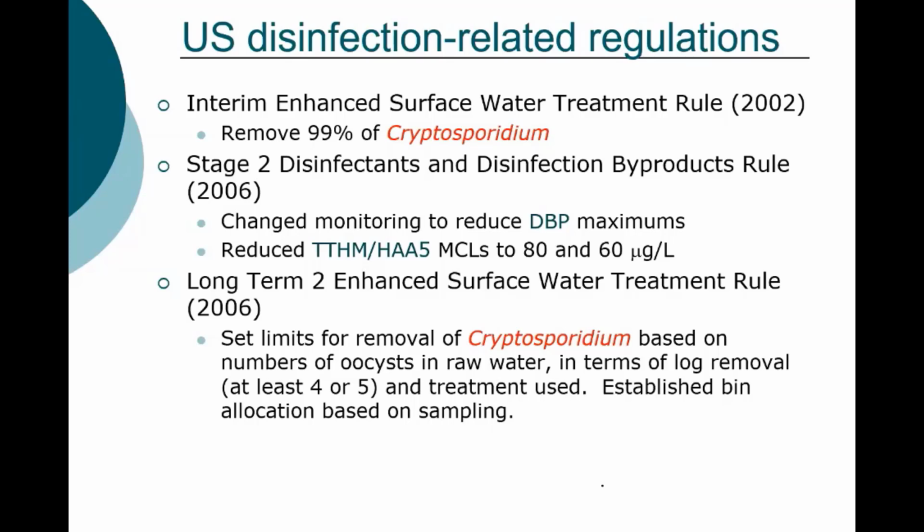It also reduced the levels for total trihalomethanes to 80 and haloacetic acids, and there's 5 of them, to 60. And the way this is measured is with what's referred to as a locational running annual average.